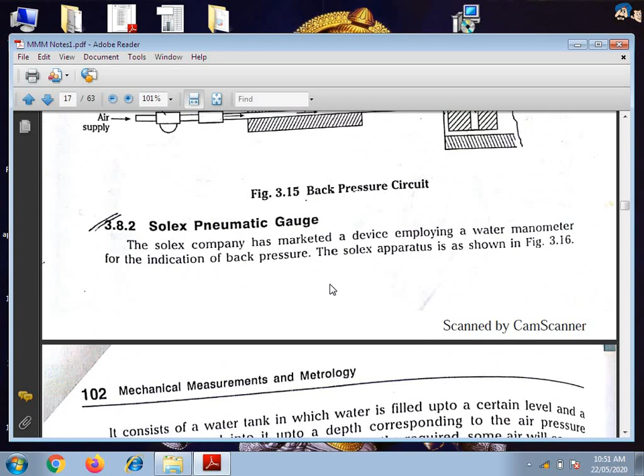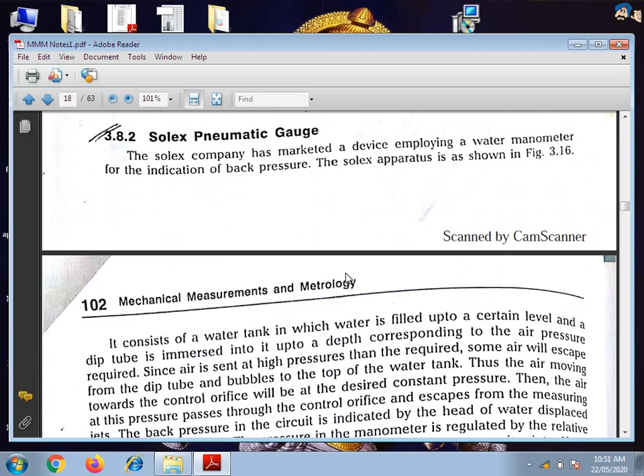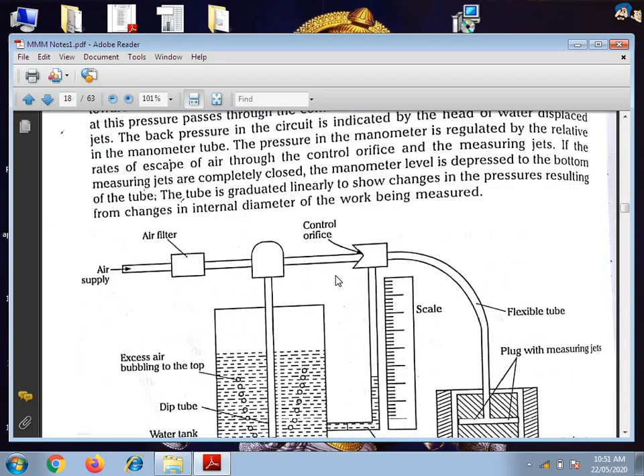Next, one more important comparator: the Solex pneumatic comparator. Here again, air is supplied and filtered, and before that, excess air bubbles out to the top. This is the water tank, dip tube, and manometer. The manometer is the tube, having scales so that variation can be observed. The air from the filter enters the water tank, and if there is excess air, bubbles will escape out, and it passes through the controlled orifice towards the measuring head.